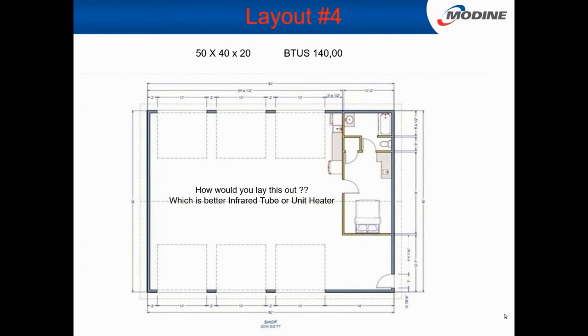Any input? Yes, 2 infrareds. Yep. Flip, power pins on opposite ends and both hung in the center, 45 out, shooting towards all the cold air. That's a good application. Remember, the building's only 40 foot, so if you hang it at 45 at 15 feet, well, this is a 20-foot building, you're gonna have way too much throw. So you might be better off flat. Put them exposed to the garage door flat, because that way you're gonna get your coverage. At 45, you're gonna heat so much up the sidewall that you're losing all that heat.